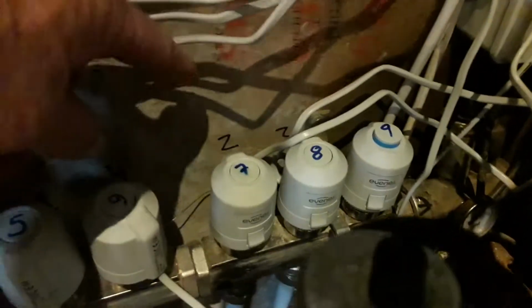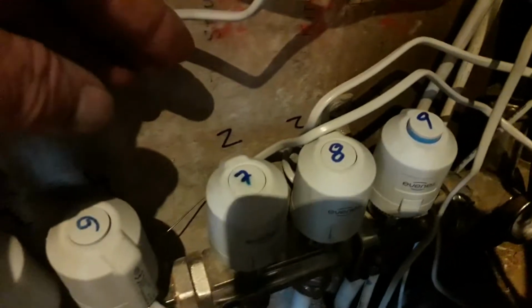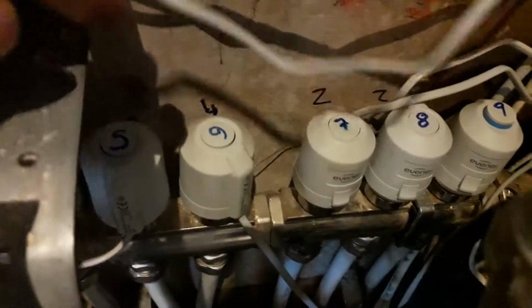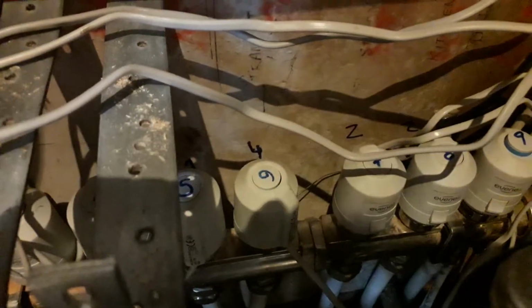And so that example in terms of the loop actuators is fine, because we had one stat in a small room, just turning on the one number 9 there. Now I know on my piece of paper number 1 is what we started with, but it can be any number. So now I'm going to shut off this stat, and turn on the next one, which has multiple loops connected to the stat, and I'm going to show what to do there. Now we've moved on to another room, and in this house it's actually a kitchen stat, and this has two loops connected electrically to it.